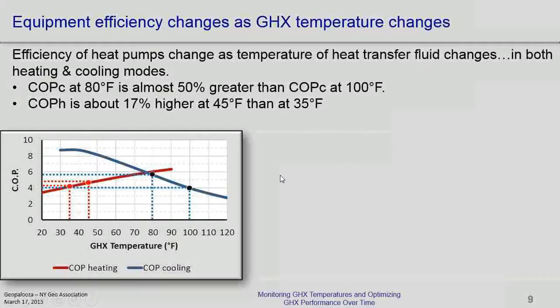So why is that important? Basically, what you're looking at is that the efficiency of the heat pump changes as the temperature of the heat transfer fluid changes. And that happens both in heating and in cooling. The COP in cooling at 80 degrees Fahrenheit is almost 50% higher than the COP at 100 degrees. When the ground heat exchanger temperature gets up to 100 degrees, the efficiency changes quite a bit, versus keeping it down at 80 degrees. Same thing in heating. There's a difference in the efficiency of the heat pump.